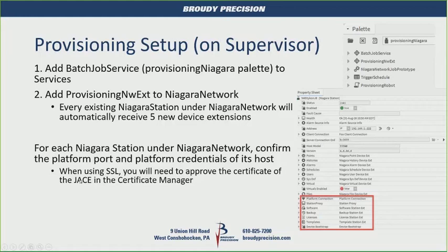One thing I made note of was that if you're going to use secure Fox, when you set this up and you connect, you're going to find that the certificates will need to get approved in platform in order for it to actually work. That's typically standard anyway when you're using Fox S between a supervisor and a JACE. You're going to find that your Niagara network doesn't log in until you get the certificate approved. That's just a matter of going to your certificate manager, going to the far rightmost tab, finding that certificate that has the little shield that's red, and just approving it.